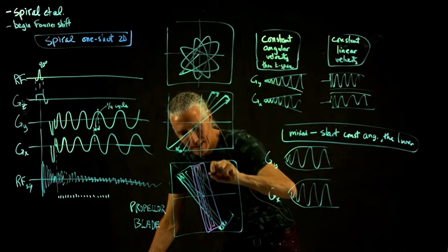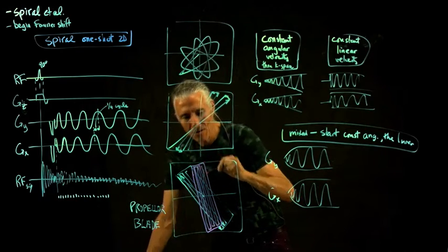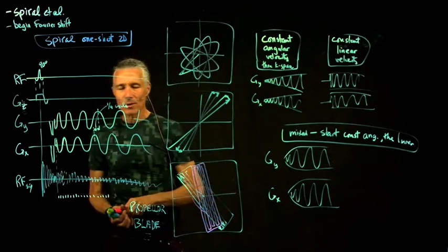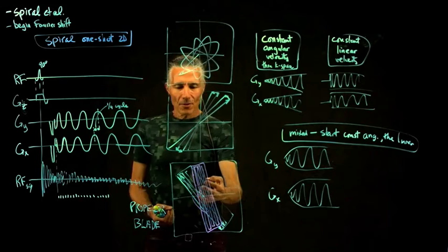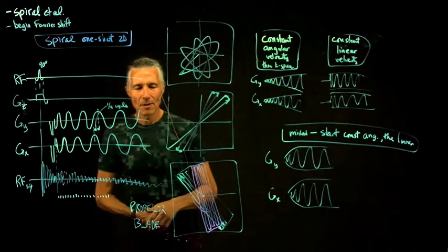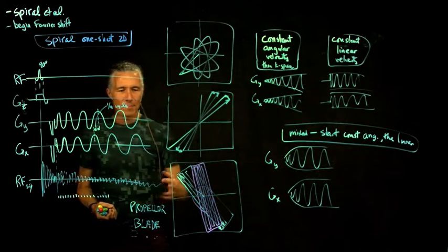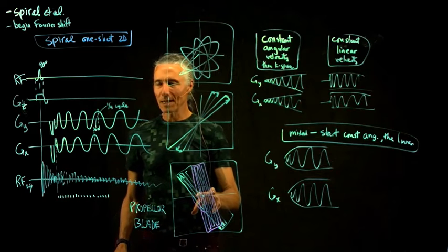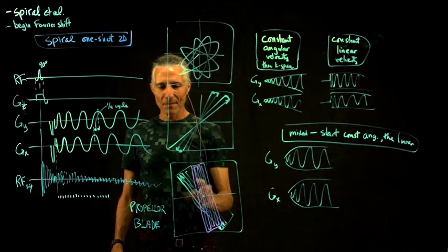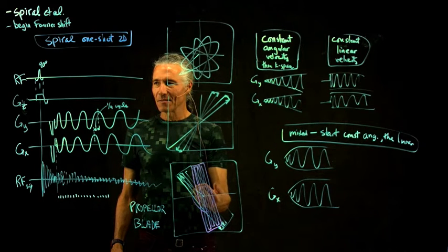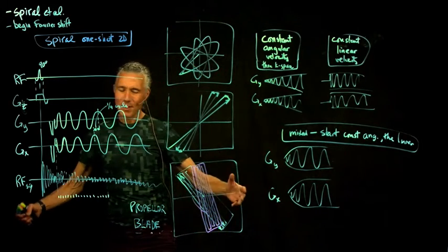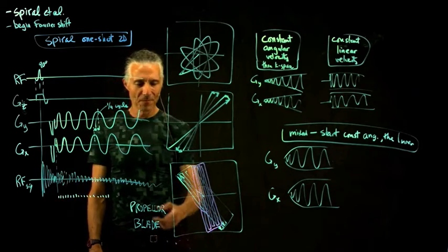One advantage of this is that you go through the center of K-space multiple times. So you can use that information to compensate for motion. Since you're going through K-space multiple times, you can measure where the head went using the center of K-space, and then effectively fix the data before you reconstruct the whole thing. So it's yet another method of motion control.